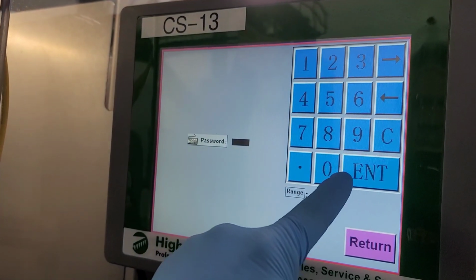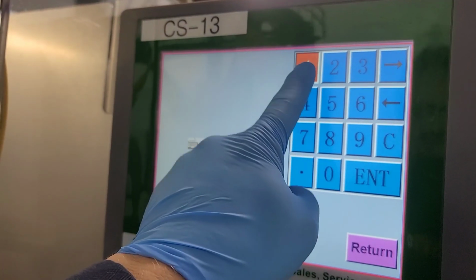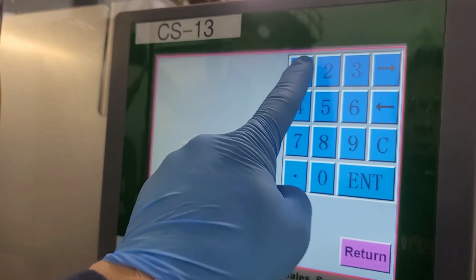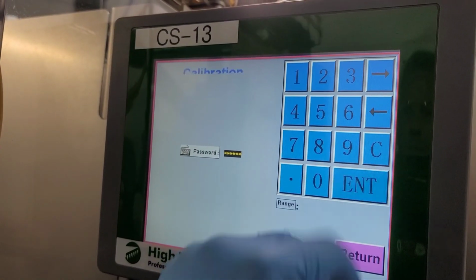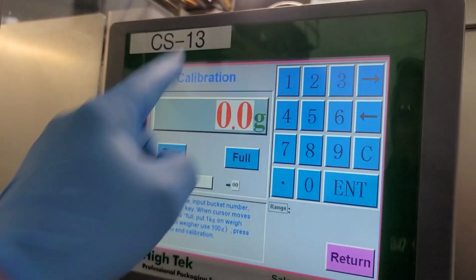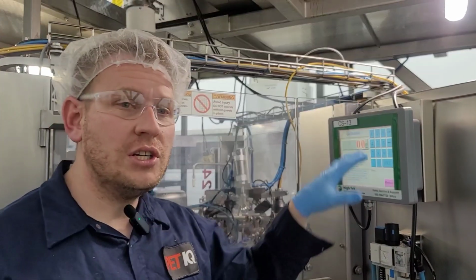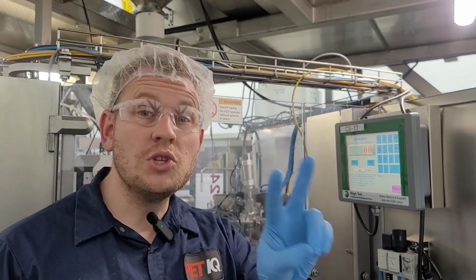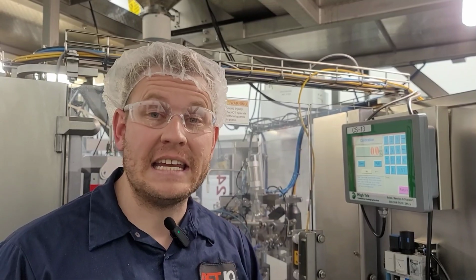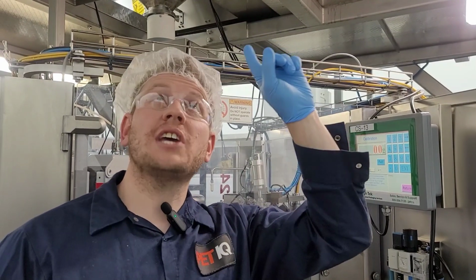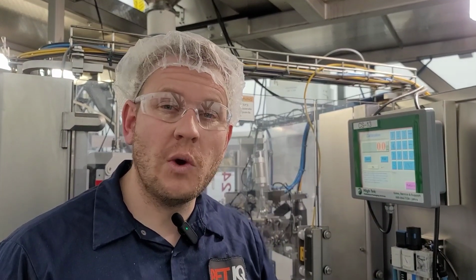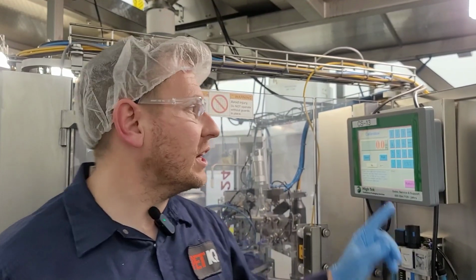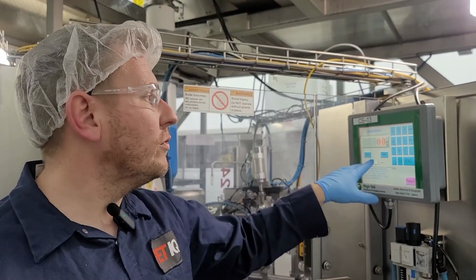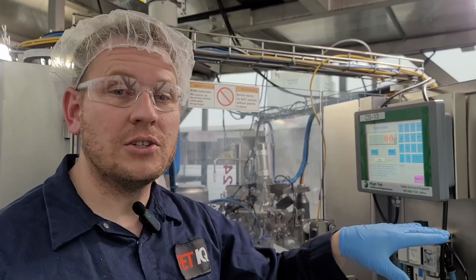Go ahead and show it. The password is typically all ones to enter the calibration menu. This operation typically requires 2 technicians to make it faster and easier. 1 technician on the scale above to move the calibration weight from bucket to bucket, and 1 technician down here moving from one bucket to the next to perform the calibration.